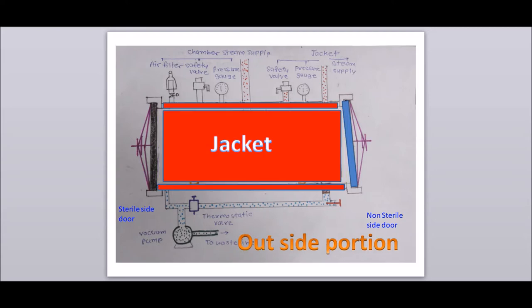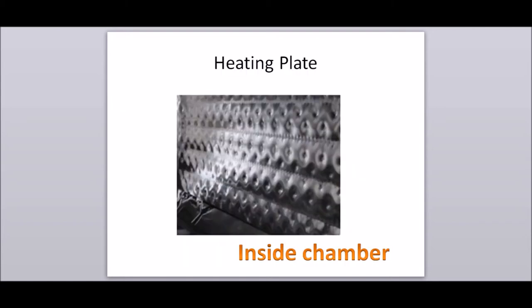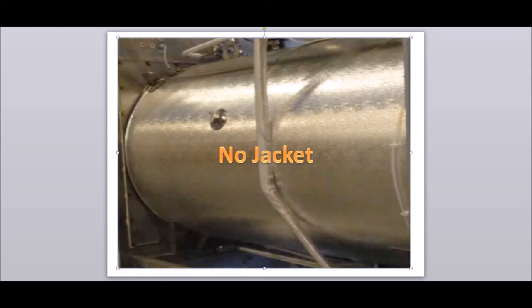The second part is the jacket of the autoclave, which covers the chamber. In some autoclaves, a jacket is not provided. Instead, a heating plate is provided inside the chamber. In this case, there is no jacket and the chamber is insulated.